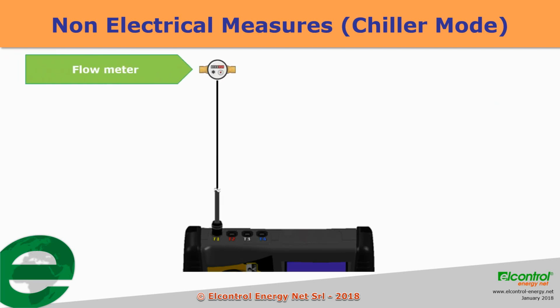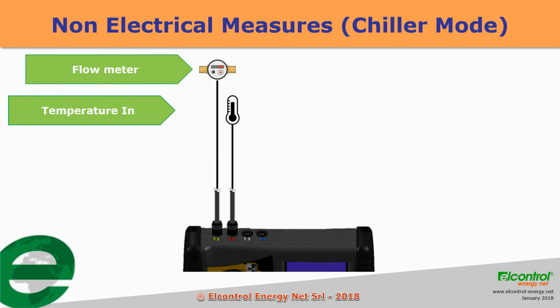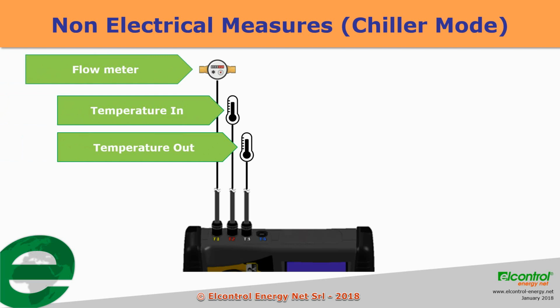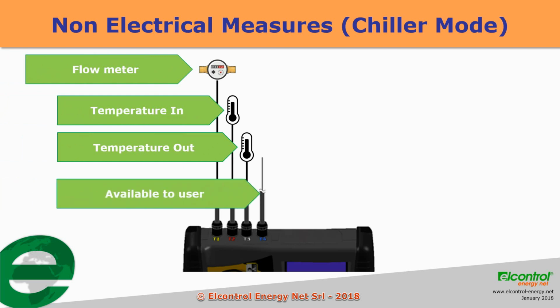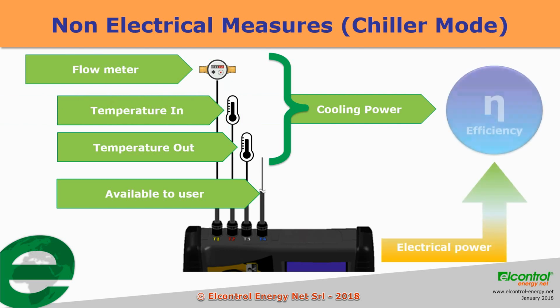Chiller mode measures chiller system parameters as well as their overall efficiency. When chiller mode is selected, NanoVIP 2 Plus will expect a flow meter connected to input T1, an inlet temperature sensor on input T2, and an outlet temperature sensor connected to input T3. T4 input remains available for any additional measure the user needs. With measures from inputs T1, T2 and T3, NanoVIP 2 Plus calculates cooling power. Electrical pump power is measured by the electrical channel. NanoVIP 2 Plus is then capable of calculating real-time chiller system efficiency.